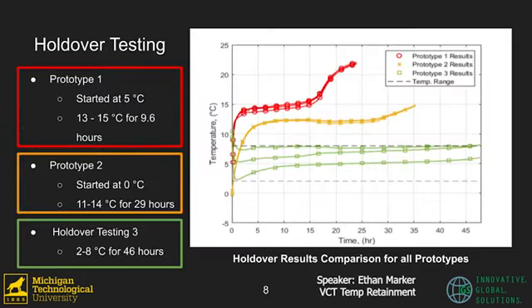Shown in this figure are the holdover test results for 3 temperature probes for each of the 3 prototypes made throughout the course of the project. Prototype 1 held a temperature range of 13 to 15 degrees Celsius for 9.6 hours. This was unsatisfactory because the temperature range was outside of the required 2 to 8 degrees Celsius, and the holdover time was significantly below the minimum 30 hours.